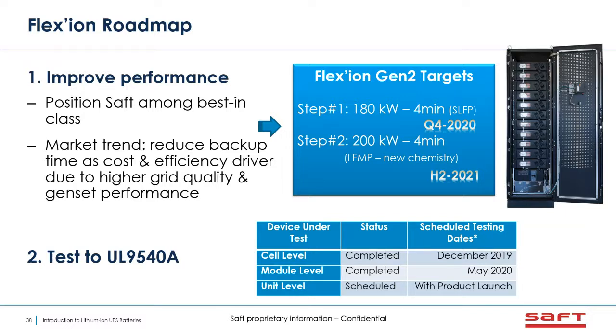The other thing we needed to do was catch up with codes and standards by testing our system to UL 9540A, the large scale fire test I mentioned earlier. We've already completed our cell level and module level testing, and our unit level cabinet testing is slated to be completed with the product launch. The interesting thing about the module level test is that we proved with UL that our modules don't propagate fire cell to cell—we can set off a thermal runaway event inside the battery modules and the rest of the cells are not affected. That's a huge win, a strong signal that our chemistry, cell design, and safety are correlated through UL.